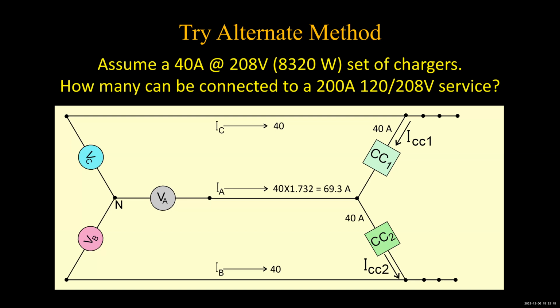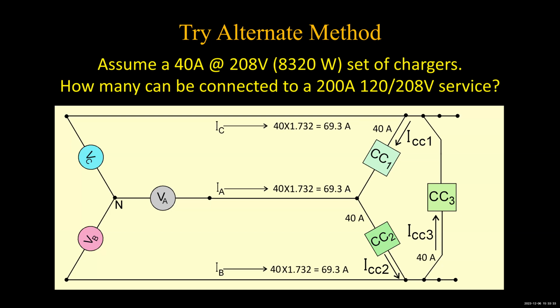And if you've got your handy clamp-on ammeter, you can measure the current. And if you want to go into phasor analysis and fancy math, you can prove it. But this 1.732 is the difference in the currents between these two lines. So we've got 40 amps in line C, 40 amps in line B, and 69.3 in line A. A little unbalanced, but it's not 80, it's 69.3. So now let's put in a third one. Now we've got 40 amps for charge controller 3, 40 for charge controller 1, 40 for charge controller 2. What effect does that have? We now have two of these charge controllers connected to each of the three lines, so each of the three lines is going to have 69.3 amps rather than 80.